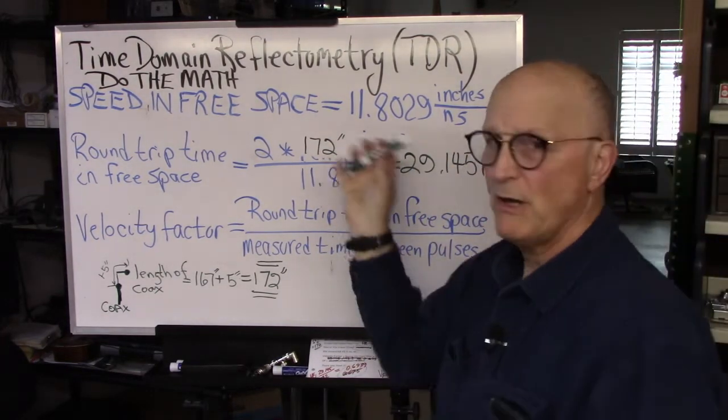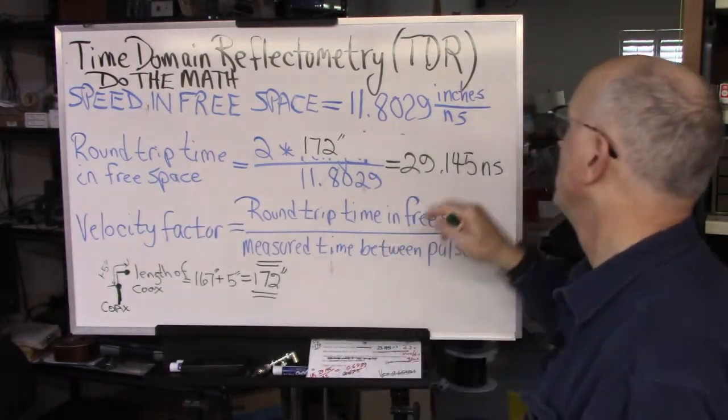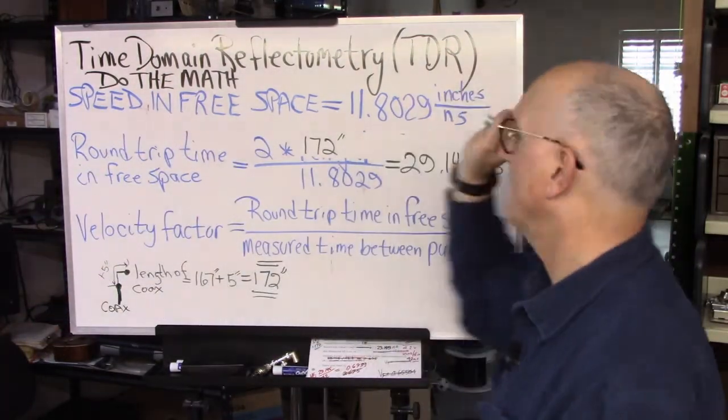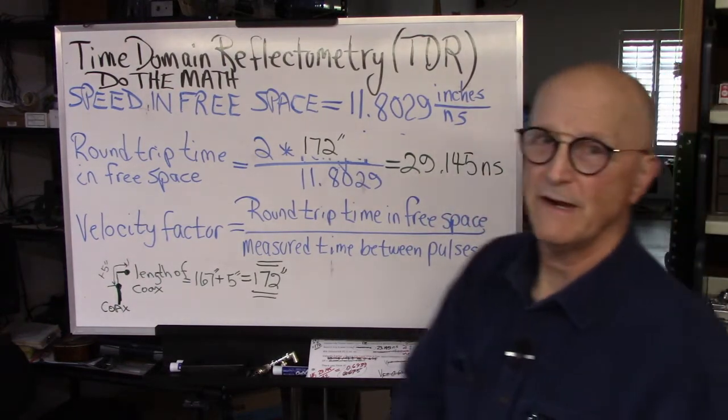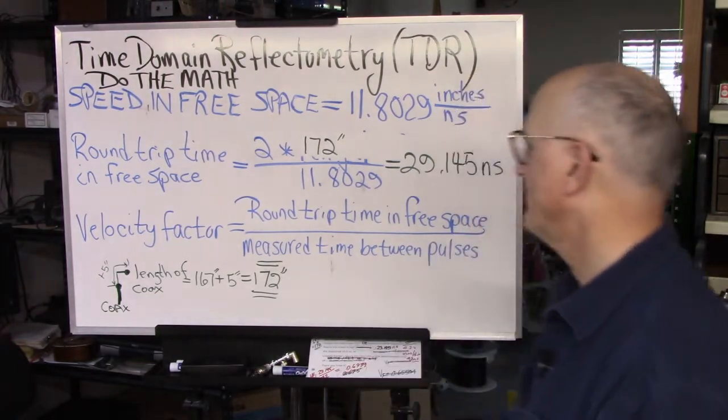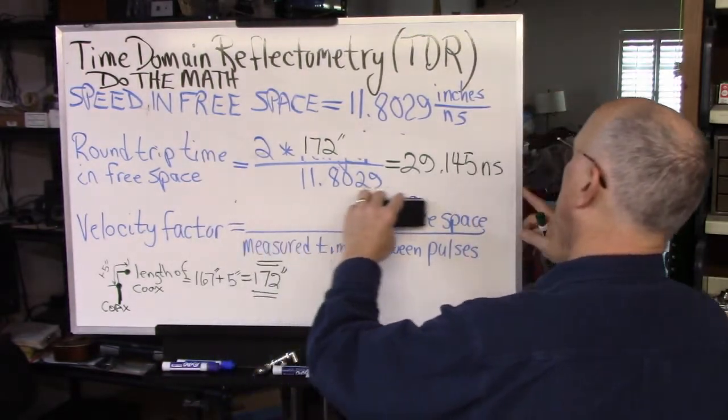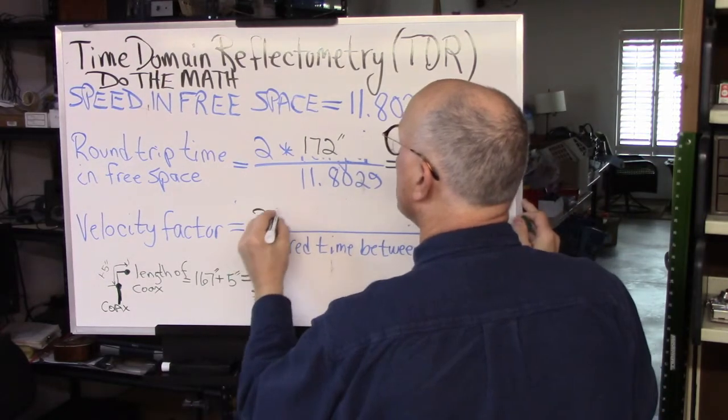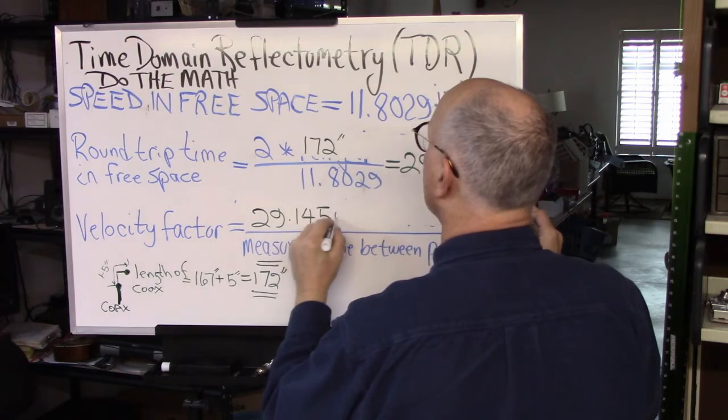So if this pulse was traveling in free space, unencumbered, to go out to the end of the coax and back again, would be only 29.145 nanoseconds. But the reality is, it's traveling more slowly than that. So the round trip time in free space then is 29.145 nanoseconds.